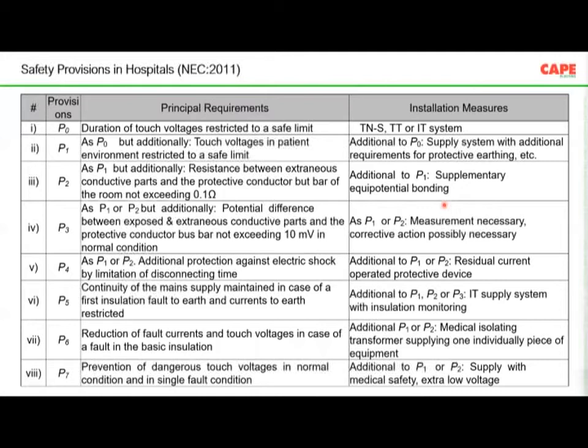Now, the National Electrical Code 2011 also gives you some indication of the kind of protective provisions required in a hospital, in a medical location. However, NEC 2011 will probably be replaced by an NEC 2022 within 2-3 months. But I would recommend that the provisions of NEC 2011 can also be followed, because detailed information is provided. So different safety provisions are recommended in the standard, starting with P0, P1, P2, P3, P4, P6. You can see it here, different provisions, and the explanations are provided.